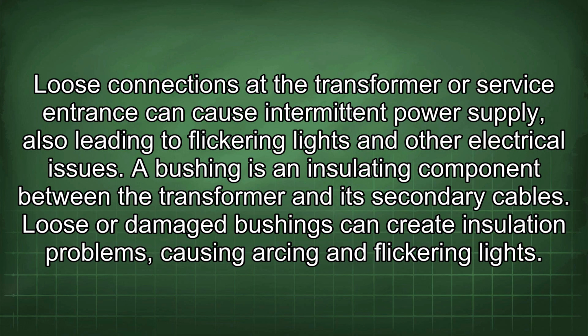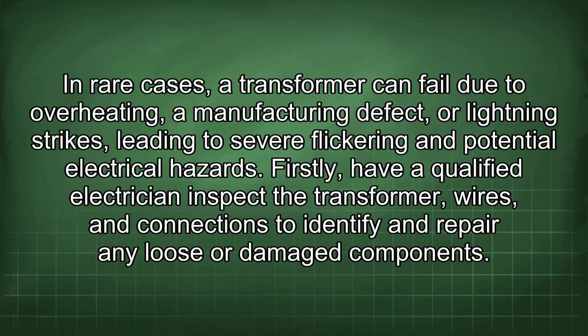and other electrical issues. A bushing is an insulating component between the transformer and its secondary cables. Loose or damaged bushings can create insulation problems, causing arcing and flickering lights. In rare cases, a transformer can fail due to overheating, a manufacturing defect, or lightning strikes, leading to severe flickering and potential electrical hazards.